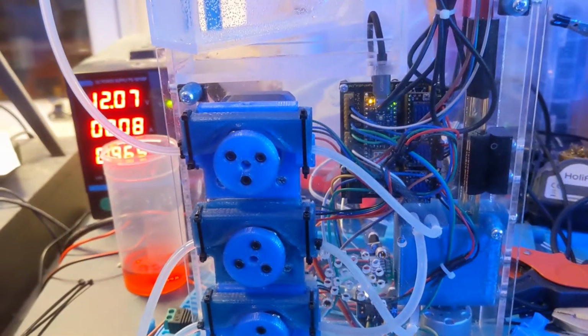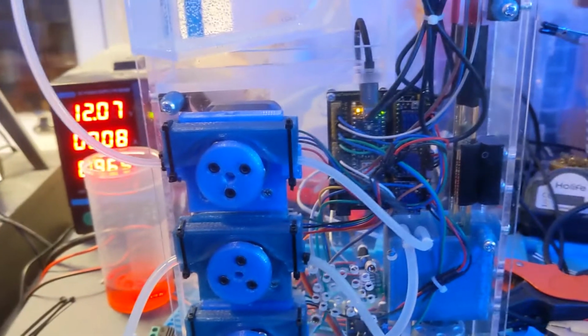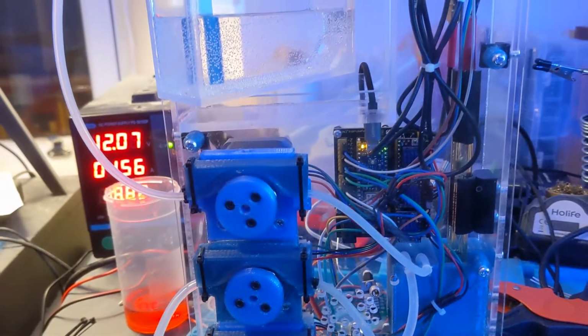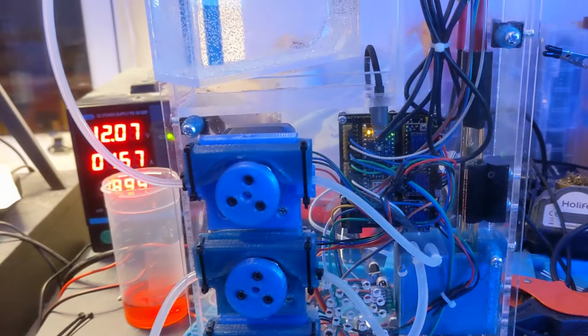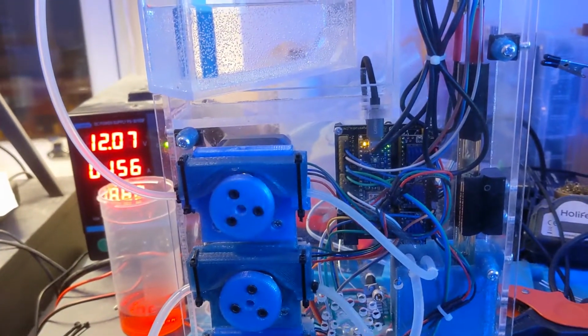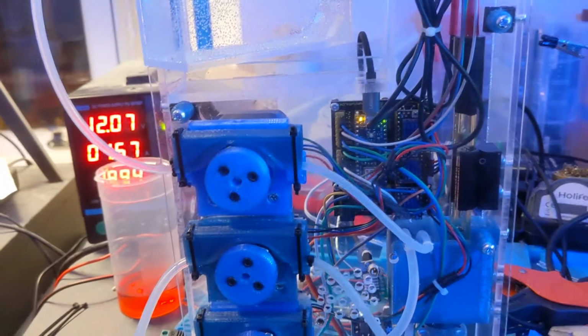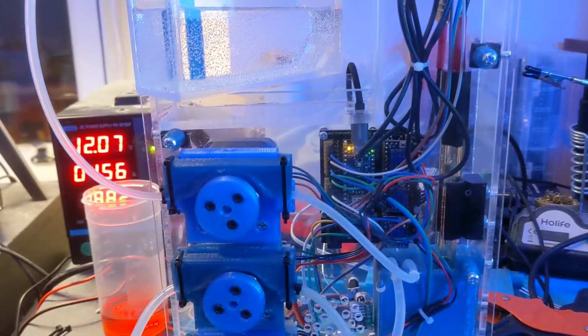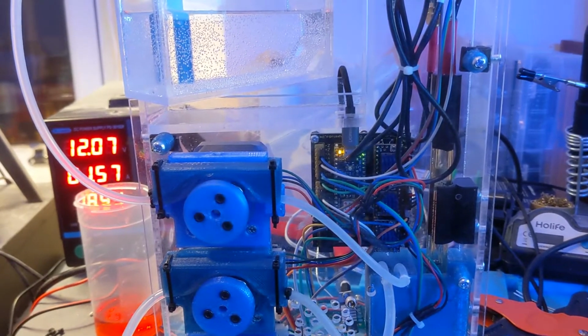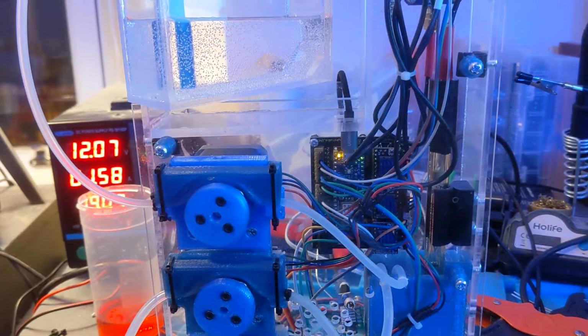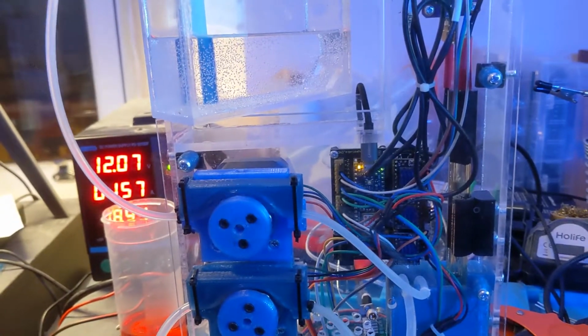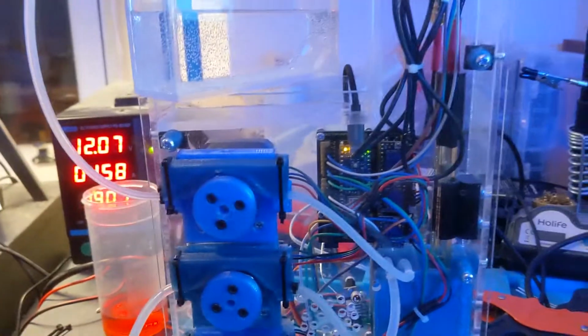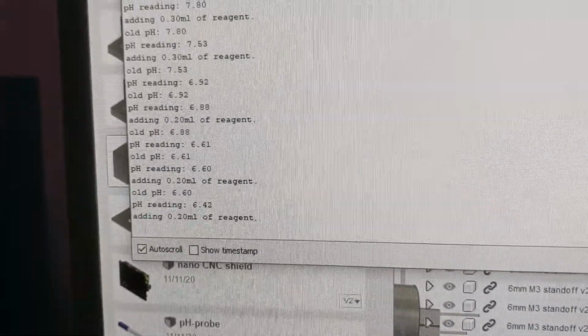Once the pH has dropped below 7.5, it moves into the medium speed titration, which does the same thing, but with 0.2 milliliter doses. And then once it's dropped below 5.5, it goes into the slow, which is 0.1 milliliter doses. What that does is keep the sort of precipitous drop from happening and taking us way past the target 4.2 pH. Right now, according to my serial monitor over here, we have gotten down to 6.4. So it's continuing to add in that medium speed.